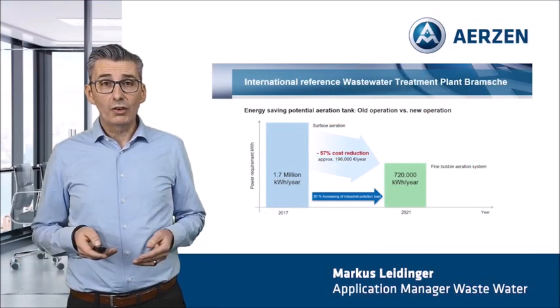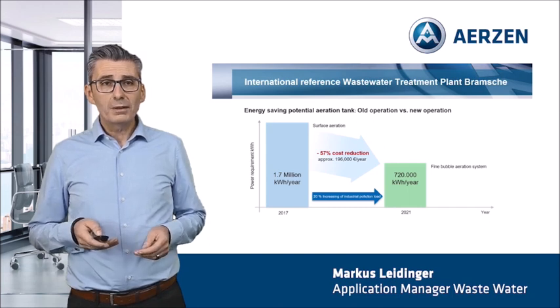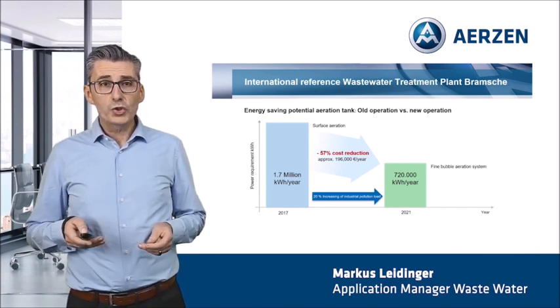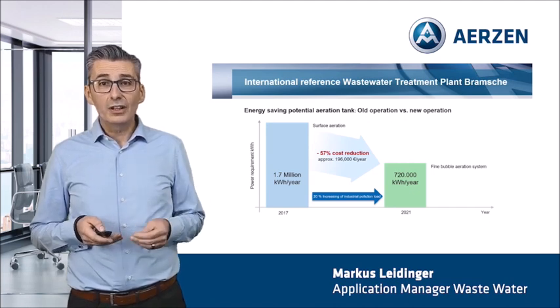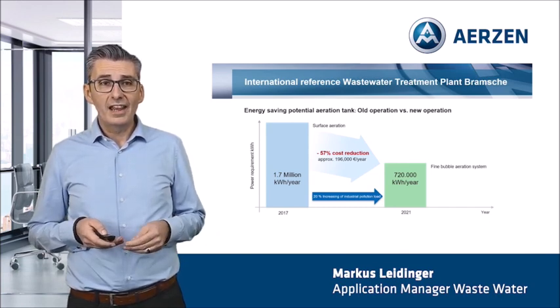What is the result of the new installation? Therefore, we look at the power requirement in 2017. We need 1.7 million kilowatt hours per year. You can remember we have a 20% increase of the pollution load up to 2021. But in this year, we only need a consumption of 720,000 kilowatt hours per year with the newly installed fine bubble aeration system. And that means we have cost savings of 57%, and these are approximately 200,000 euros per year.